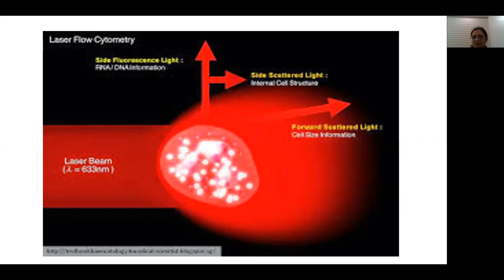Coming to this illustration to show you the fluorescent flow cytometry, wherein the cells in a diluted sample flow through the flow cell as a single file and pass the laser beam. The reflected forward angle indicates the cell size, and the side scatter or 90-degree angle scattered light indicates the complexity of the cell.